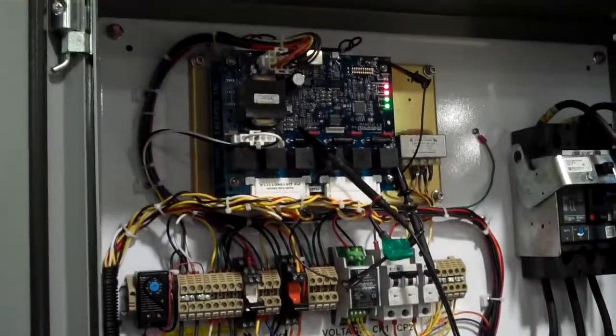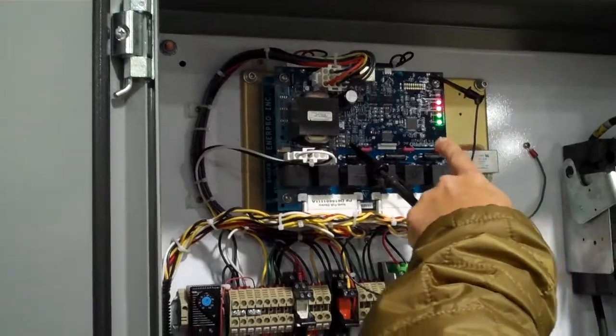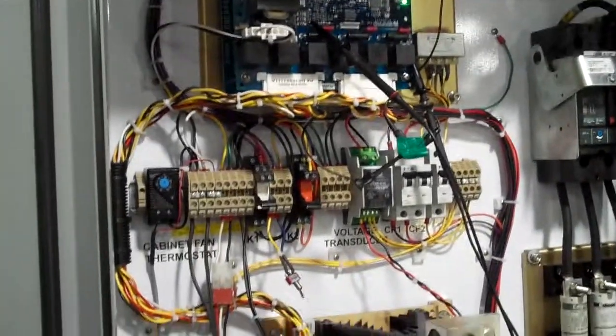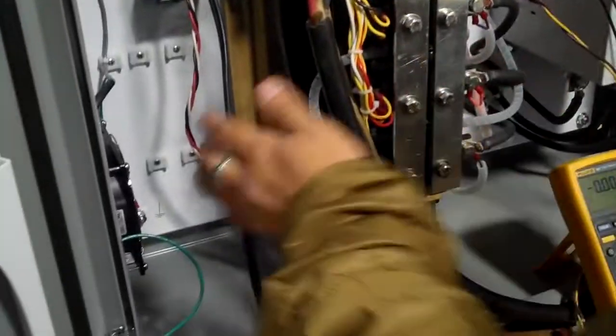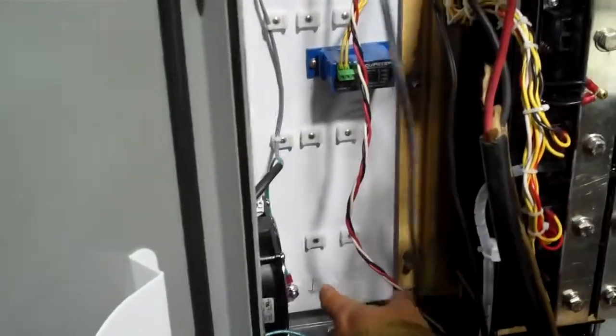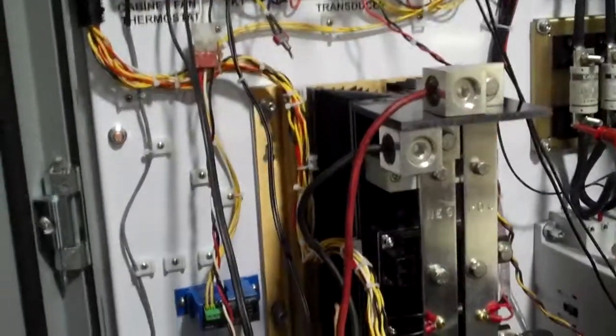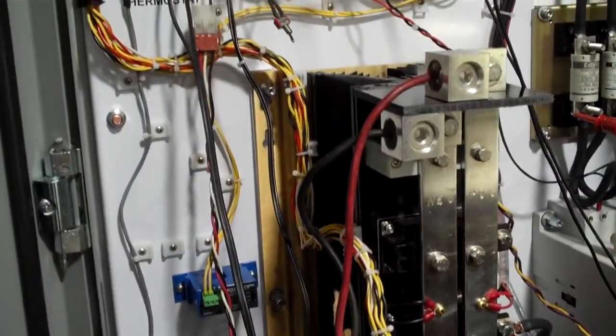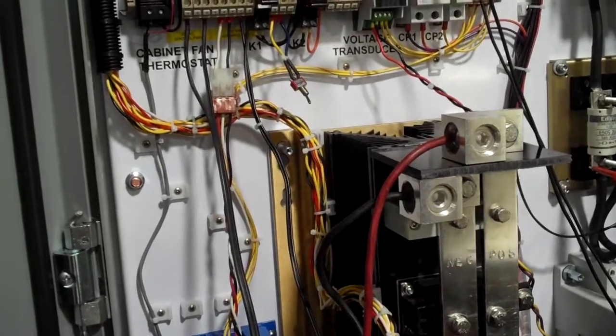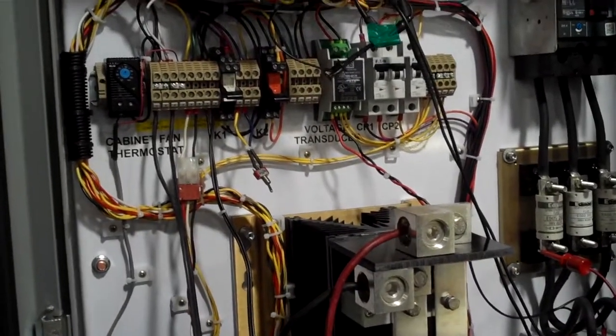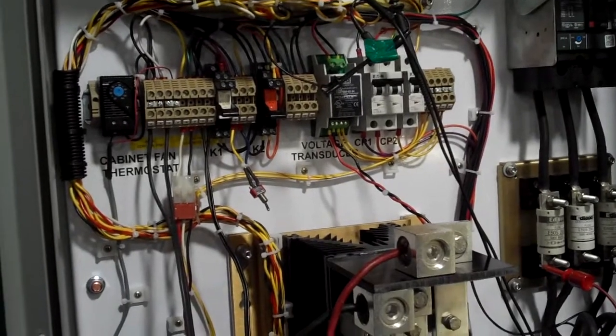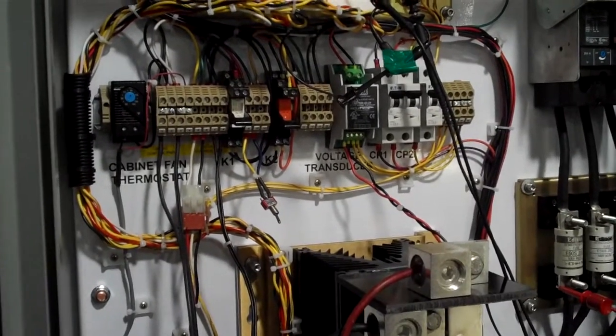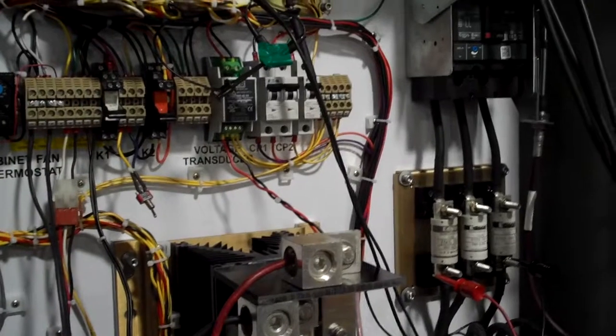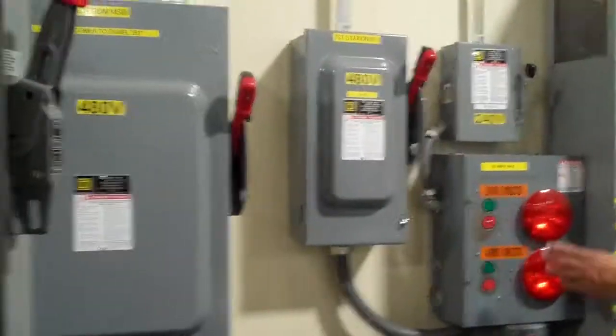This is the 120 volts that provides power to the board, to the bridge fan, and to the cabinet fan. The cabinet fan's already on because of the setting of the thermostat. This one will probably not come on because it's not going to get up to temperature; if it hits a temperature of around 60 C, then the thermostat will close and the fans will turn on. And now I'm going to go ahead and ask Tony to bring in the line through the breaker. That's the 240.